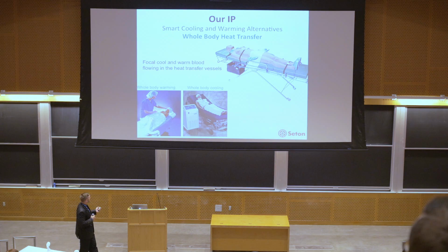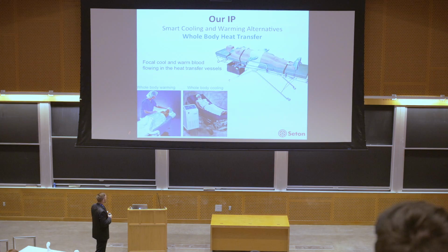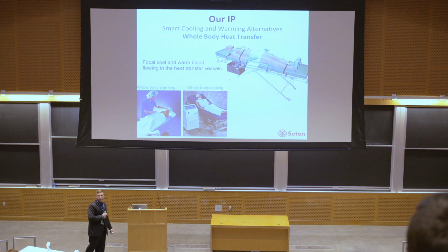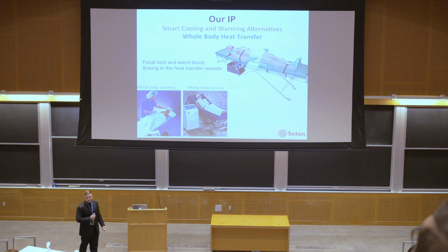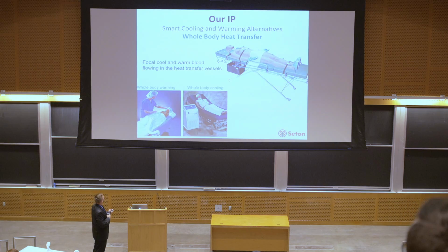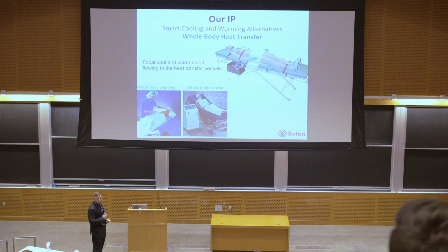Our IP is different than most medical devices in that currently we use in the operating room something like a Bair Hugger suit or some whole body warming and cooling, and it's very impractical when you're going into the operating room because it's very cumbersome, over-encumbering. What we have is just a simple neck heating and heat exchangers, and you have a little water reservoir with thermal fluid system and good to go. Set up and put down in a couple minutes.